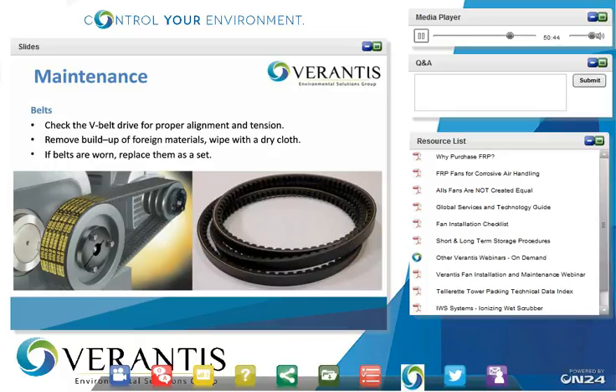Okay, check your maintenance. Again, check your V-belts for proper alignment and tension. You want to remove any buildup of foreign material from the sheaves, especially if you've had one where the belts have been slipping. A lot of times you'll get material buildup in the bottom of the groove of the sheave. That needs to be removed. Wipe it with a dry cloth. And if the belts are worn, replace them as a set. Do not install one or two new belts and about four old belts, because the length is definitely going to be different in the belts and you just cause premature wear on the new belts.